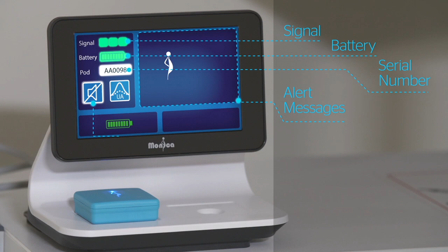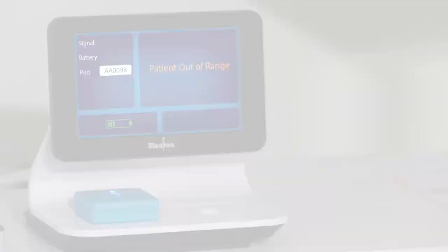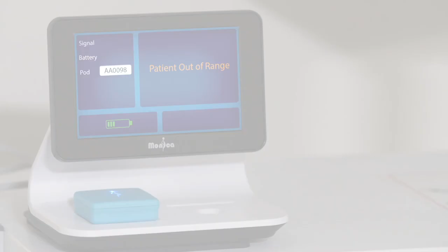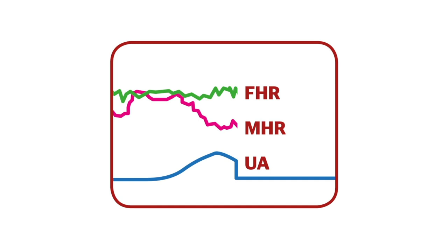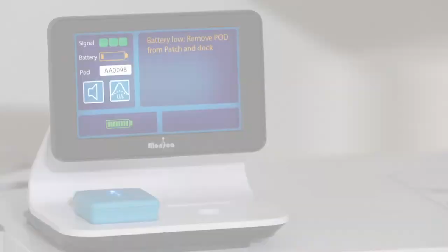Alert message examples include a poor fetal ECG signal. The 3 green squares will change to 1 red square and no FHR will be traced. This will be picked up by the fetal monitor as a signal loss alert. Mom is out of range. For the mom to move freely in the room and bathroom, you will need 3 green squares on the Novii display, indicating a strong fetal ECG signal. The Novii interface also needs to detect a good Bluetooth signal, and moving outside into the hallway may cause the patient out-of-range alert message to be displayed. The FHR and MHR trace data will be lost, and the UA will flatline. You will need to ask the mom to move back into the room if you want to continue tracing. No other action is required.